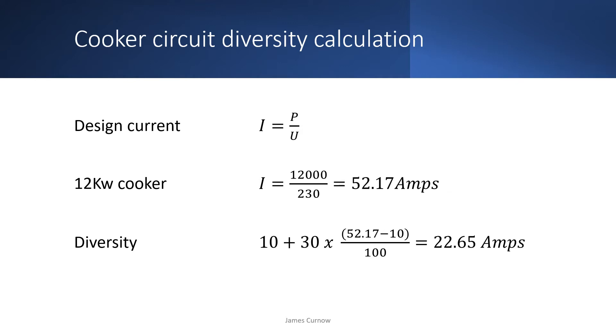The diversity can be applied by using this formula which can be done in one step on a calculator. By having 52.17 minus 10 in brackets, that gives us the remainder. Then by dividing by 100 and multiplying by 30, that gives us 30% of the remainder. By adding 10, which is the first 10 amps, we can then add the 5 amps if there is a socket in the cooker outlet.